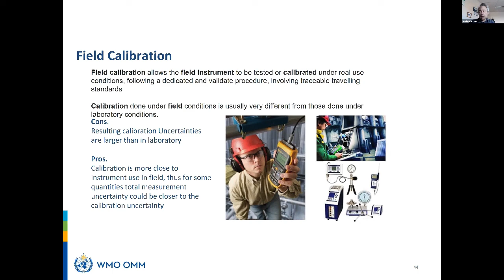But please, let's not confuse validation with calibration. If you want to make a calibration, you need to bring not just a thermometer and put it close to your sensor, your meteorological station. This is a validation. You need to bring with you a liquid bath, a chamber. Maybe you can make a calibration by comparison for a radiometer. You can do that, but you need a high quality radiometer, and then you deploy it in the field, hopefully meeting all the radiation spectrum and range that you expect, and maybe you can make a calibration by comparison for solar radiation, sometimes even for wind speed and for pressure. But take care, temperature, humidity, and other quantities are not so easy.